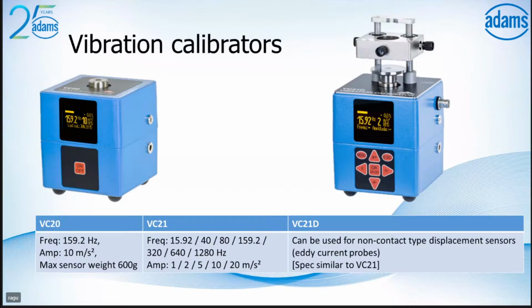The other range of calibrators that are available from Metra, so VC20 and VC21, this is a small tabletop calibrator. This is a single frequency, single G level. With VC21, you can do multiple frequencies and multiple amplitudes. VC21D is more similar to VC21, but the VC21D allows you to calibrate eddy current probes and non-contact type displacement sensors.